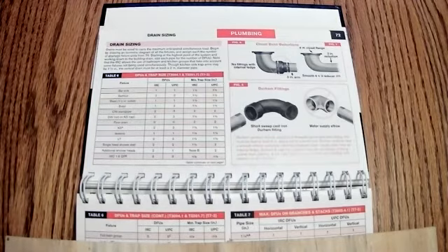Okay. Again, I'm trying to read this over my thing. Now, one of the things, the bidet, yeah. And then some bidets, okay, it says 1.5 inch outlet on it. You're going to have 1.25 inch drain. And a normal bidet under the IRC is 1, under UPC is 2. Again, I like using the UPC because it's going to oversize everything. Both of them call for 1.5 inch drains. Okay.